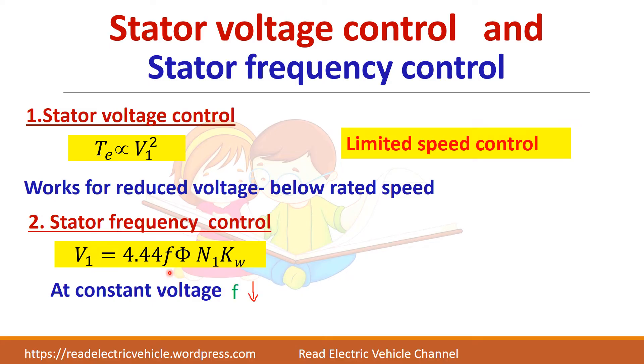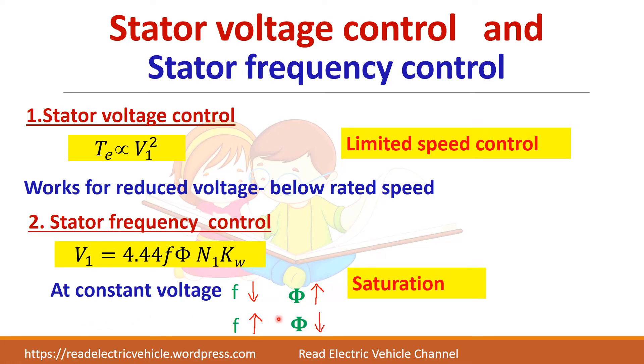If I decrease frequency, flux will increase so that voltage remains constant, but if flux increases it leads to saturation. If I increase the frequency, flux will decrease, and if flux decreases, torque will decrease — since torque and flux are directly proportional, maximum torque also decreases. This is the drawback of stator frequency control.